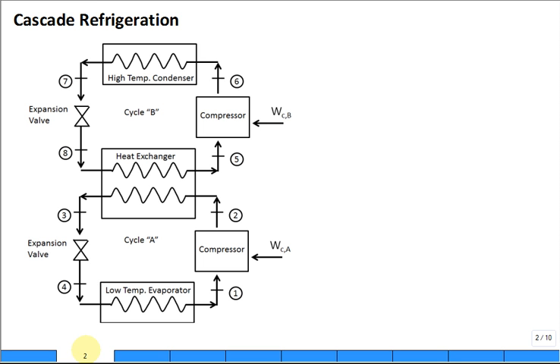What you'll have is a cycle A, it'll be a low temperature cycle, and cycle B a high temperature cycle, and they're linked by a heat exchanger where for cycle A that heat exchanger behaves as a condenser, and for cycle B that heat exchanger behaves as an evaporator.